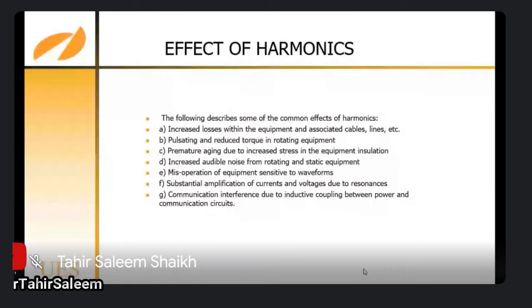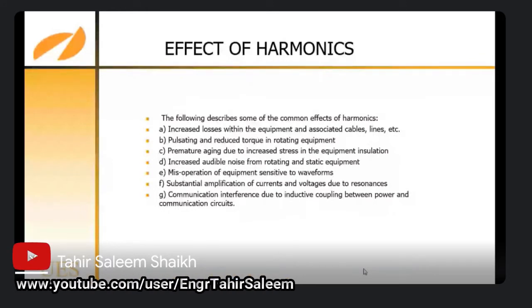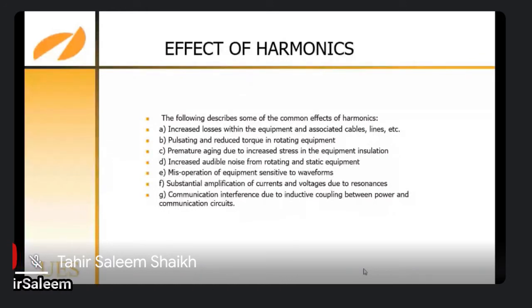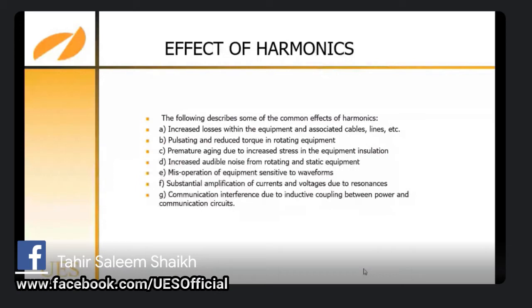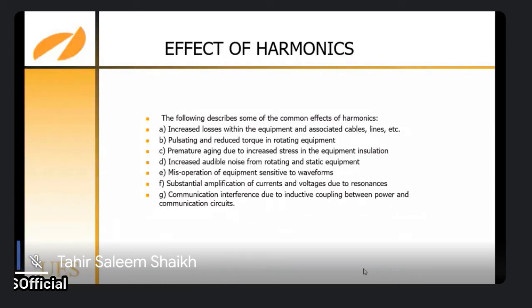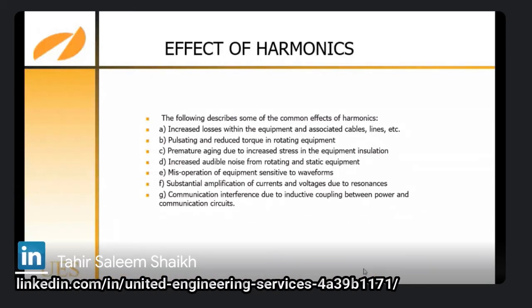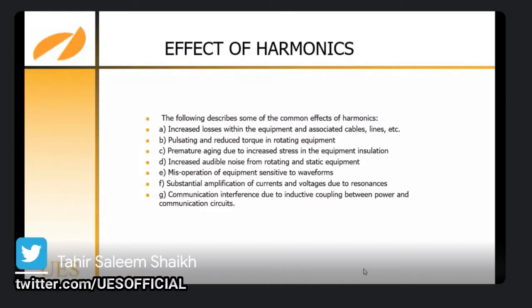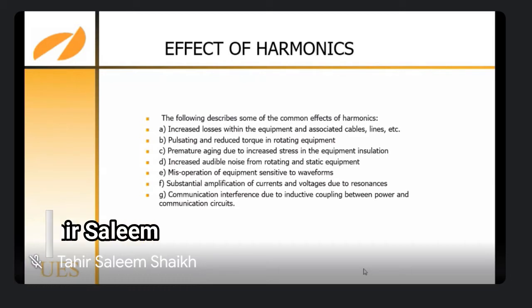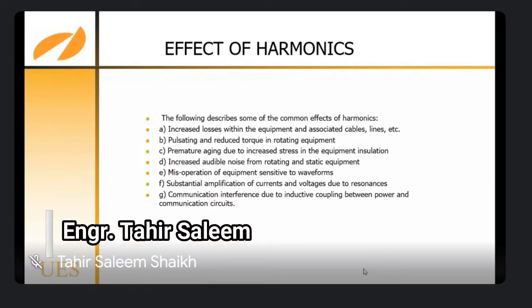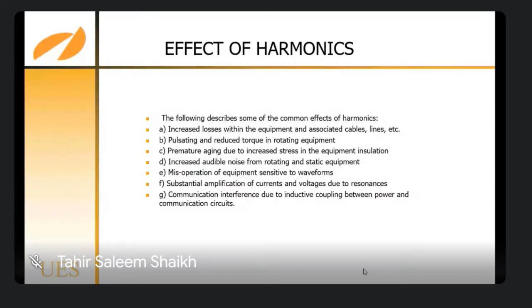Premature aging due to increased stresses in the equipment insulation, increased audible noise from rotating and static equipment, misoperation of equipment sensitive to waveforms, substantial amplification of currents or voltage due to resonance, communication interference due to inductive coupling between power and communication circuits.